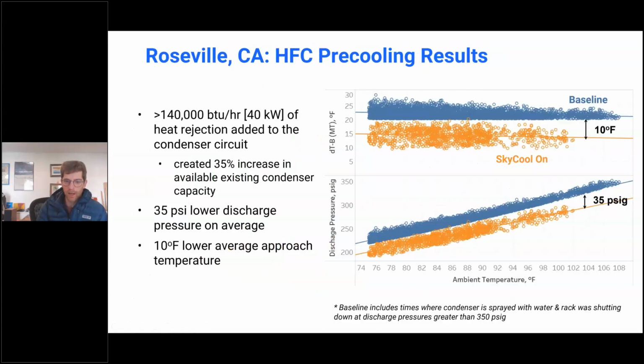As a pre-cooler, this is where the undercapacity detail is important. Previously the system's head pressure, the approach to the ambient, was much hotter than it had been designed for, because the condensers had, for example, fins with corrosion on them, and because load had grown over time as they put in new cases. So, previous summers they were seeing an approach with the ambient between 20 to 25 degrees Fahrenheit. It was originally designed for a 15-degree approach, and so by adding the panels, we're essentially able to lower the discharge pressure of the system. When the discharge pressure goes down, it reduces the power draw and improves the efficiency of the system.